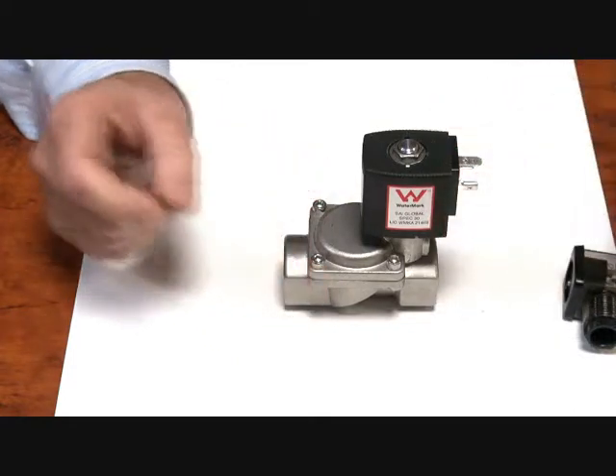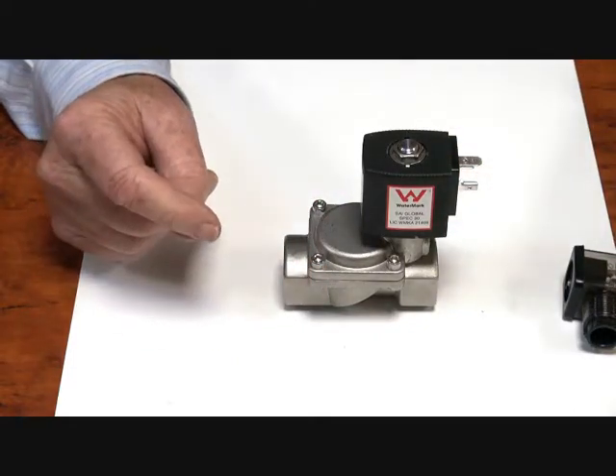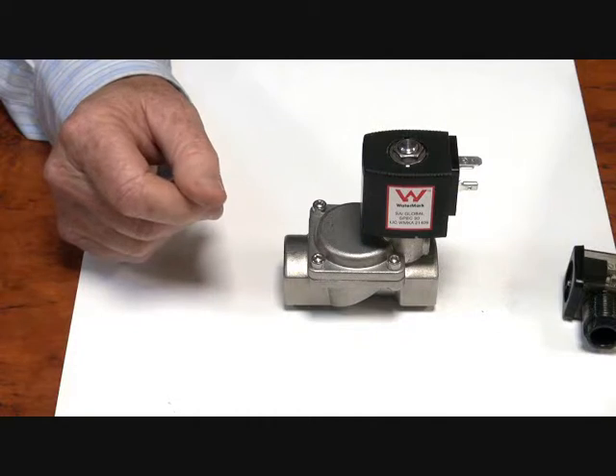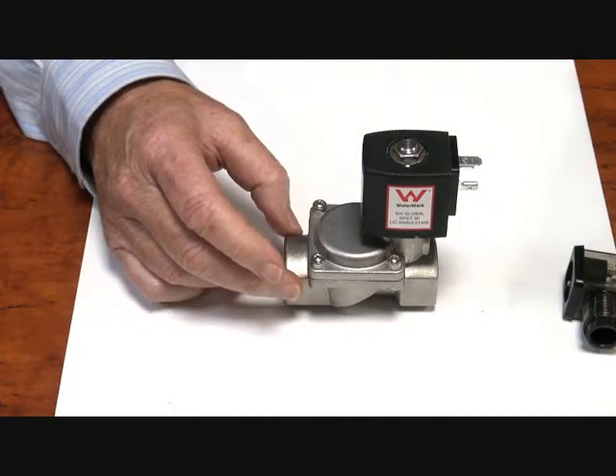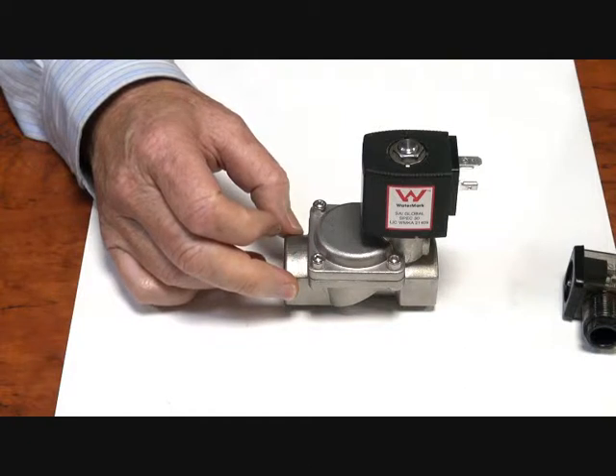The valve is a differential valve, 16 bar maximum pressure rating, 0.3 or 0.7 depending on the size. 0.3 up to 1 inch, 0.7 to 2 inch minimum differential.